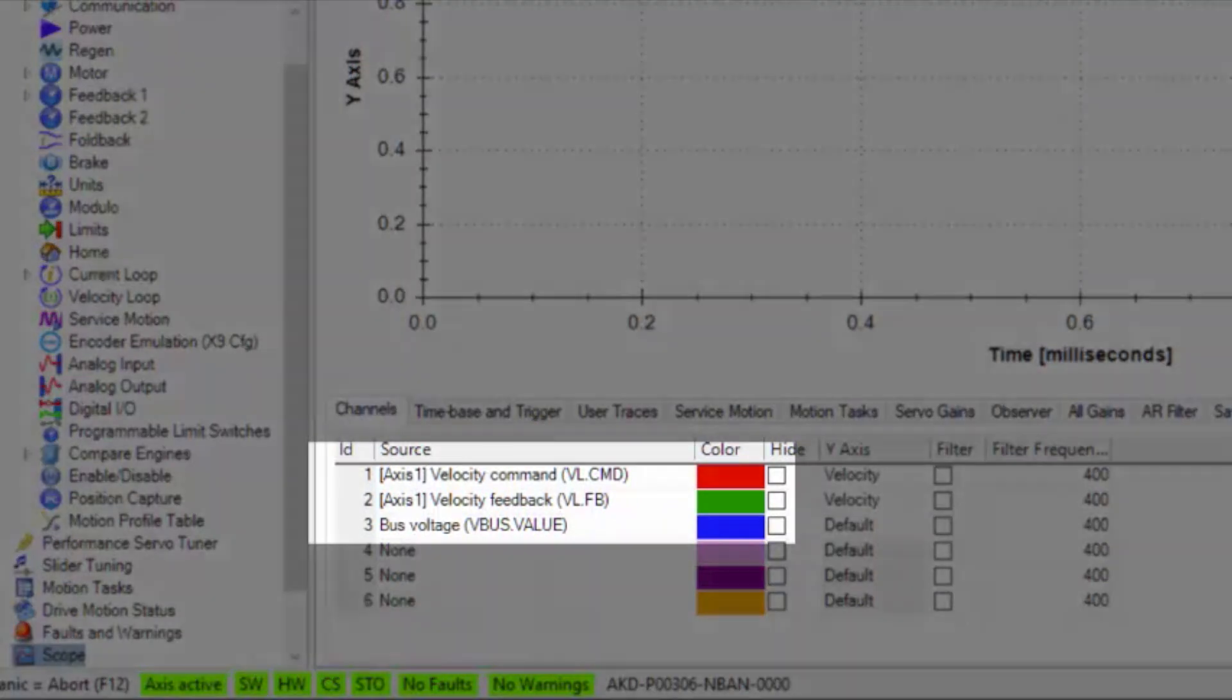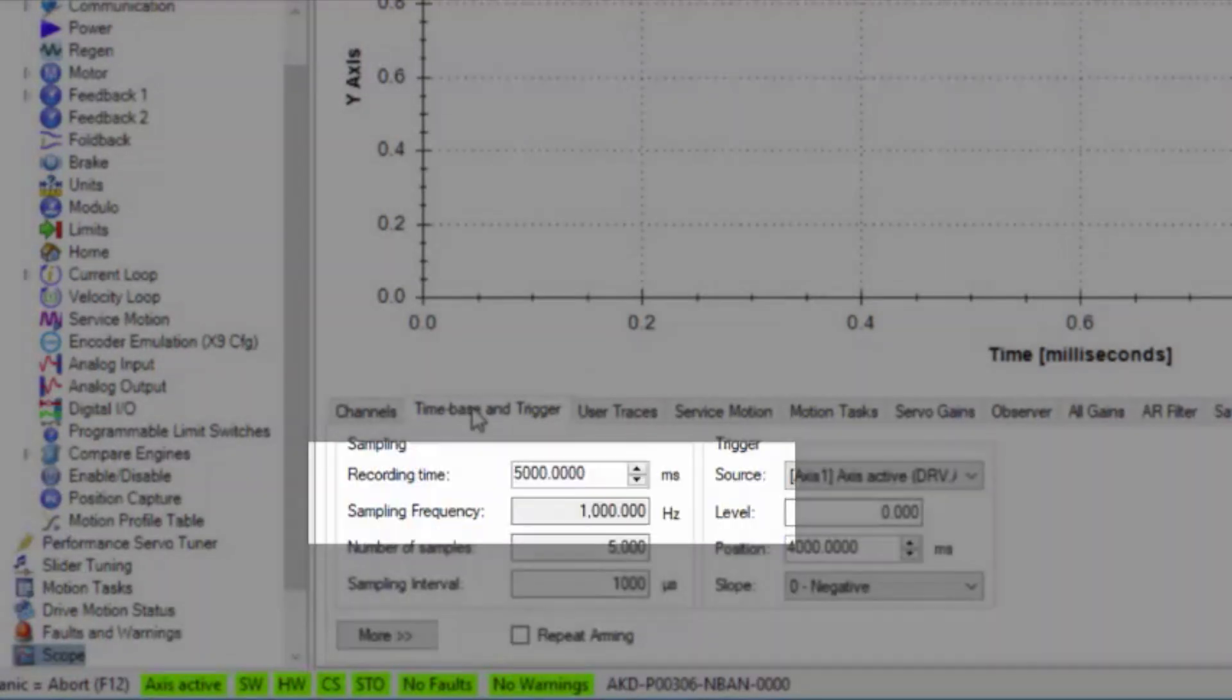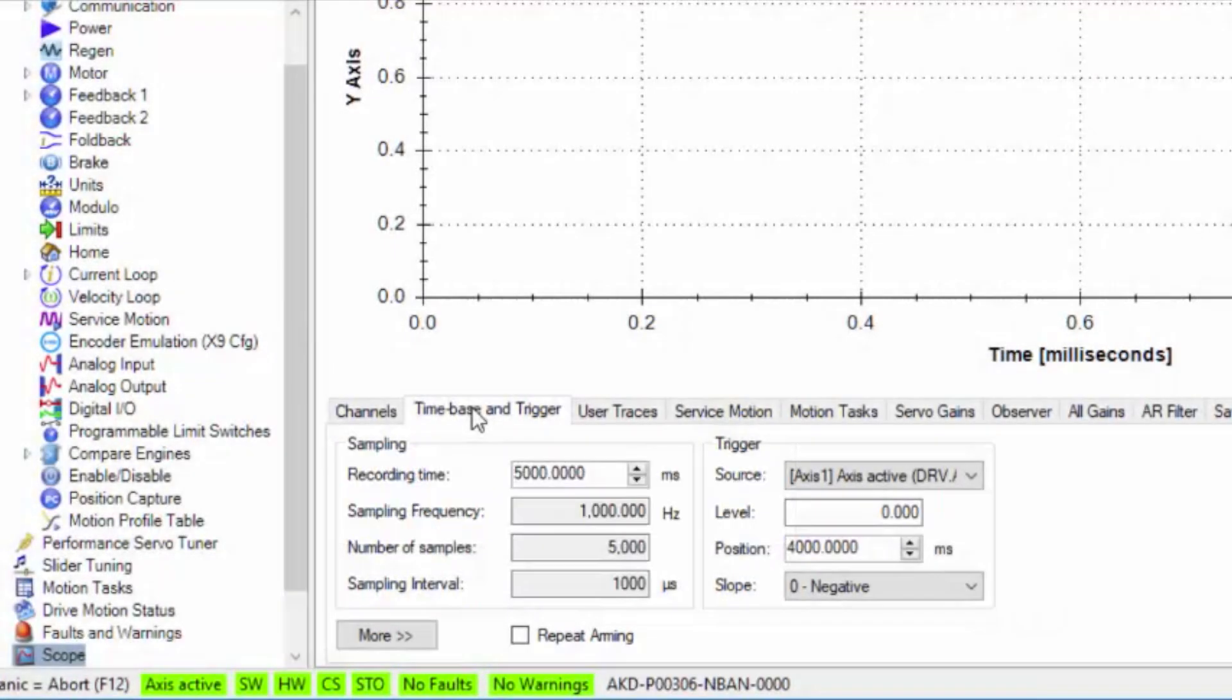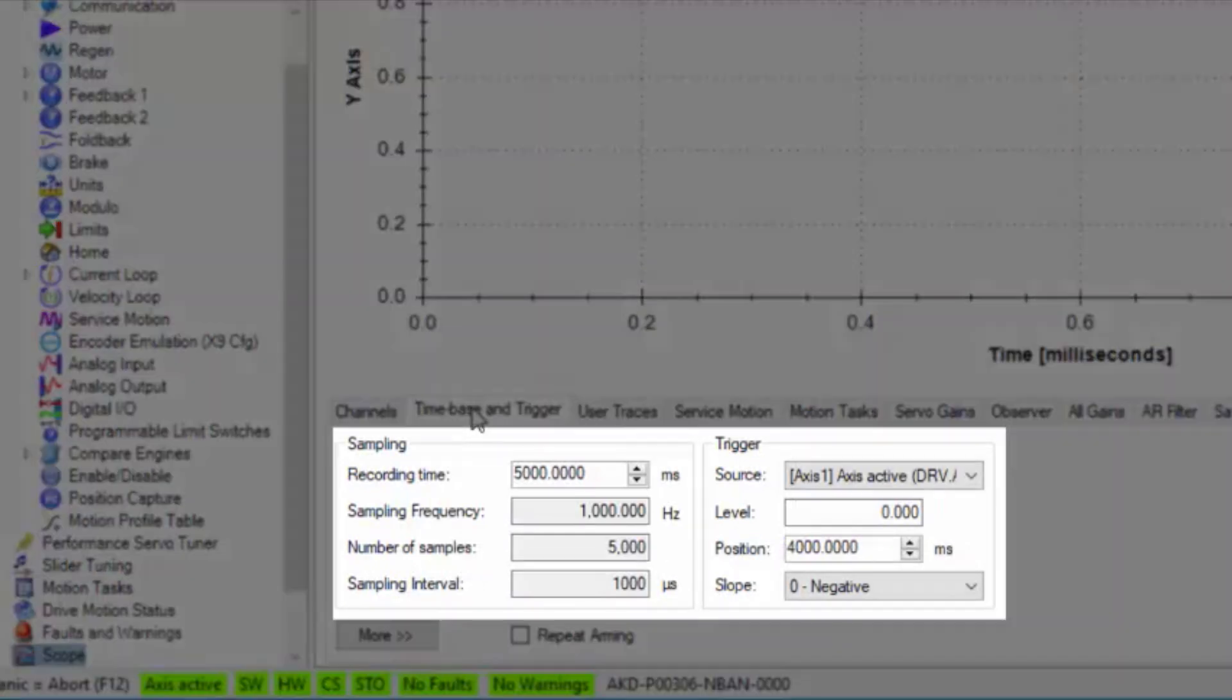We are going to set up the scope to capture the velocity commanded, the velocity feedback and bus voltage. The record time is set to 5,000 or 5 seconds of record time.